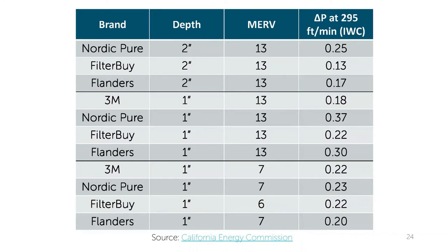Ensuring the mechanical system is designed to accommodate the selected filter is essential. The chart on this page shows the field-tested pressure drops of various filters by brand, size, and MERV rating. Ask the manufacturer for the rated pressure drop of the filter you are considering using and compare that to the system manufacturer rating for pressure drop allowance.